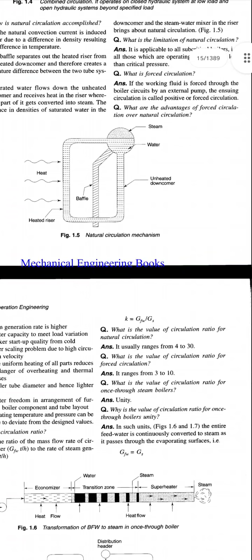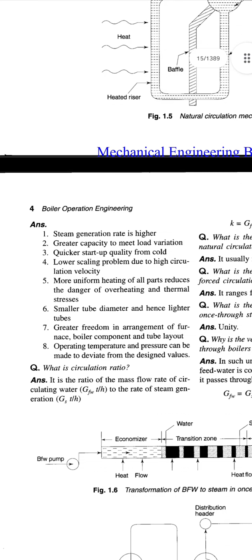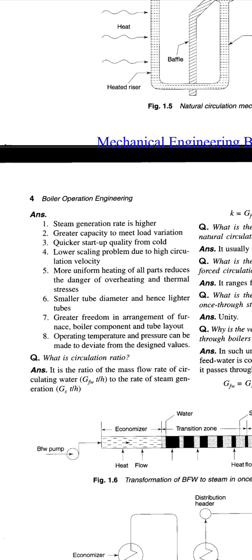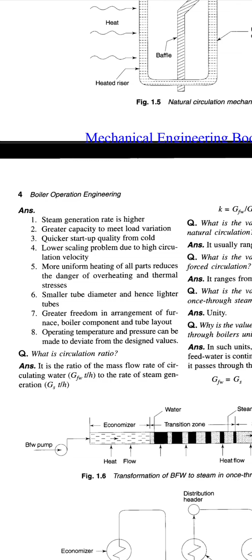Again the question is, advantages of forced circulation boiler. Steam generation rate is higher, greater capacity to meet load variation, quicker startup from cold, lower scaling problem due to high circulation velocity, more uniform heating of all parts reduces the danger of overheating and thermal stresses, small tube diameter and hence lighter tubes, greater freedom in arrangement of furnace, boiler components and tube layout. Operating temperature and pressure can be made to deviate from the design values.